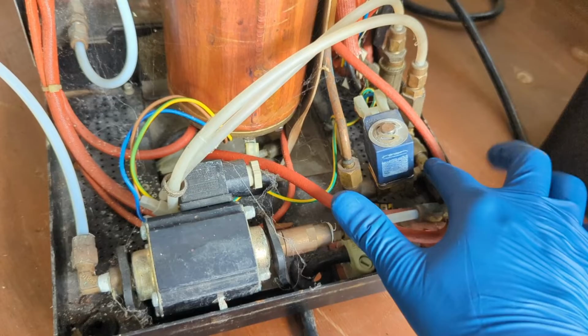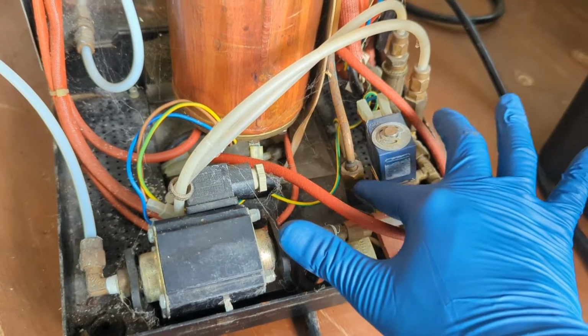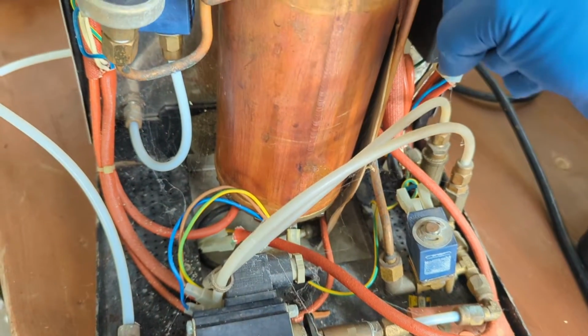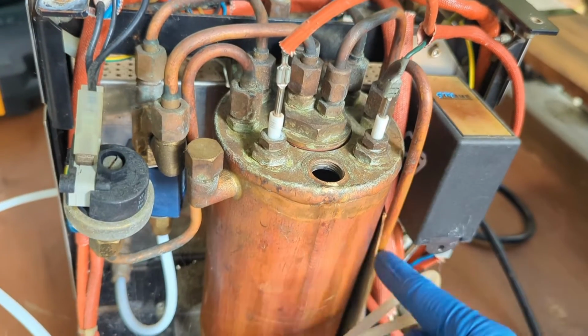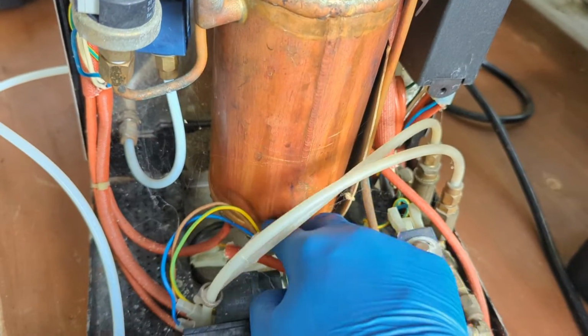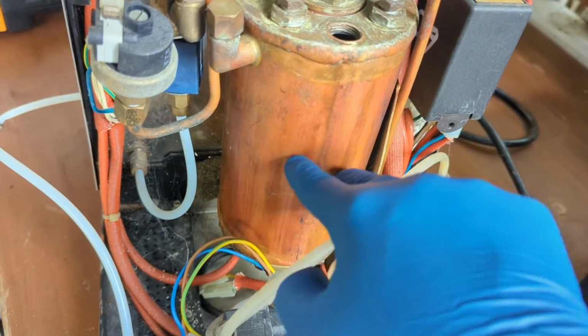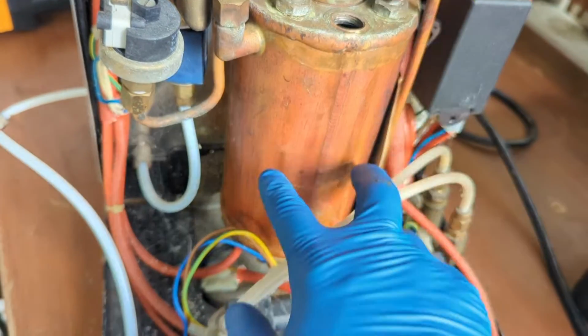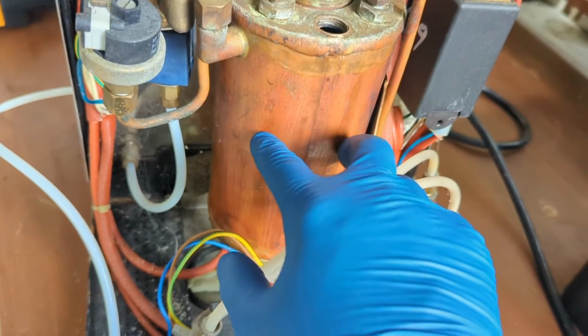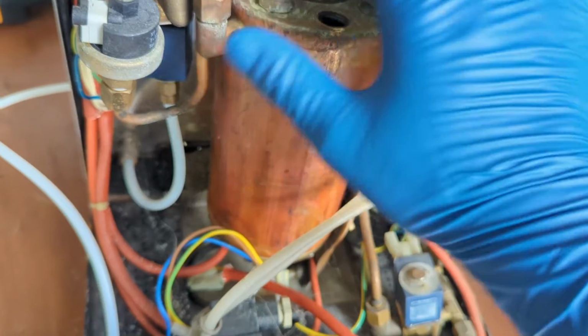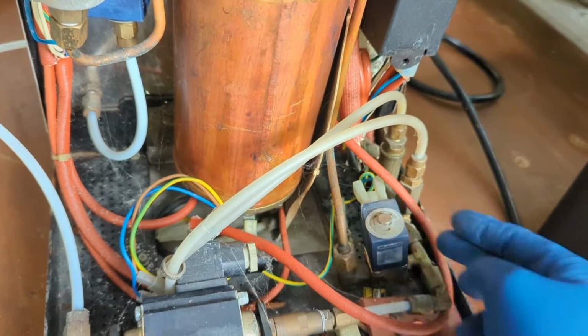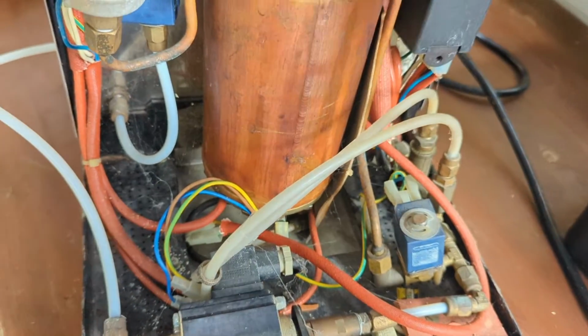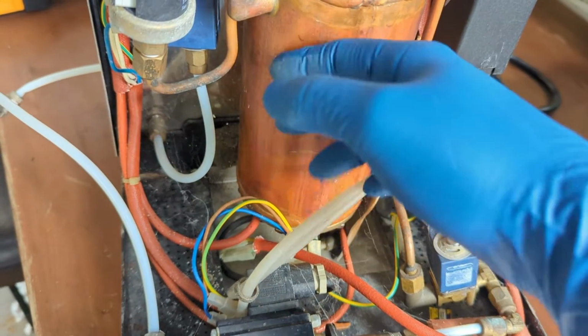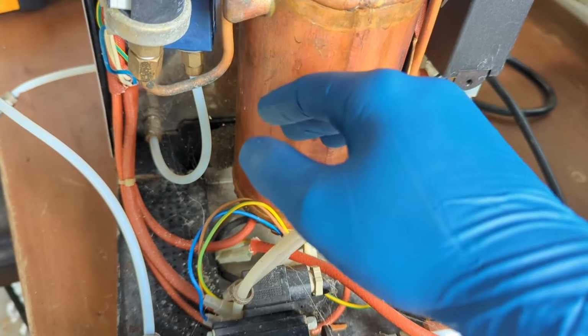This opens up, letting the water pressure go all the way to here, into the boiler, where it starts to fill up the steam boiler. Once it fills up all the way, these water level sensors that you have right here will detect the water level, and then it will just close this valve again, letting the water shoot into the heat exchanger instead of going into the steam boiler, as the boiler is already filled.